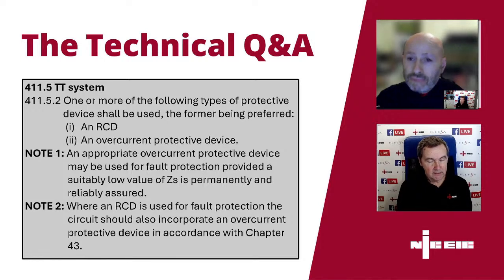I guess the kind of situation would be if you had a building with a lot of structural steel, and you were using the structural steel as your earth electrode, and because there was so much contact with true earth, your external earth fault loop impedance was so low, you could actually meet the ZS of an overcurrent protective device.